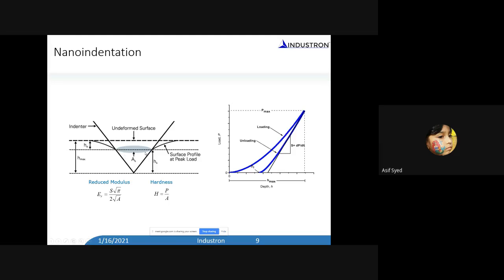What is the calculated area? Then we can take the same tip, which is basically a diamond tip, and indent on some other material for which you don't know the modulus, but we know for a given depth what the contact area is. From that calibration curve, if you know the stiffness, you can calculate the modulus of the material. Okay, this is how we measure the modulus of the material. And if you take the load divided by area, it gives you the hardness. And this is how we measure the hardness and modulus of the material. It's as simple as that.